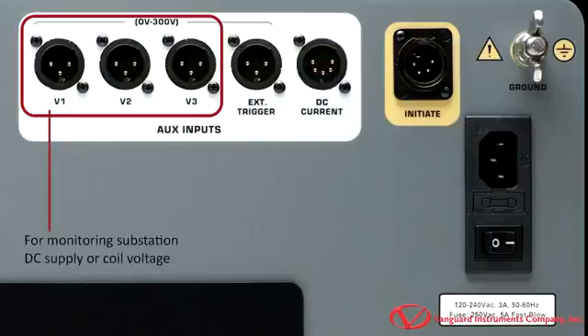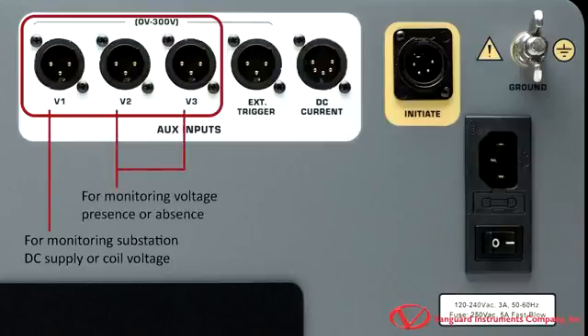These are labeled as V1, V2, and V3. The V1 voltage channel is dedicated to monitoring the substation's DC supply or coil voltage, ranging from 0 to 300V DC or peak AC. V2 and V3 are digital channels dedicated to monitoring the voltage presence or absence status of the circuit breaker auxiliary switches.